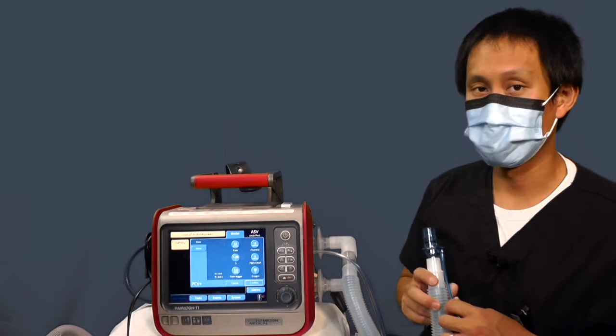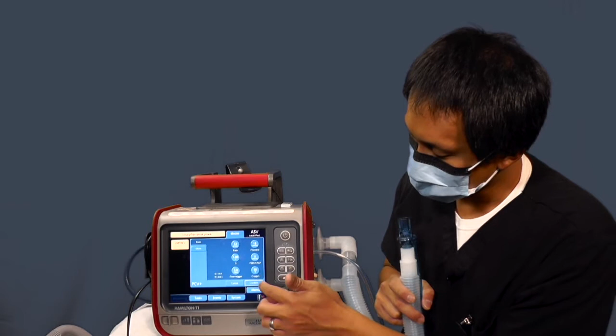So I'm going to select it, it's going to highlight it, and then I'm going to confirm to switch to that mode. Currently this ventilator is in standby, so you can put all your settings in before you place it on the patient. Okay. So what you have here is your standard pressure control mode. You got your rate, your I time, your pressure, driving pressure, your PEEP, and your oxygen concentration.